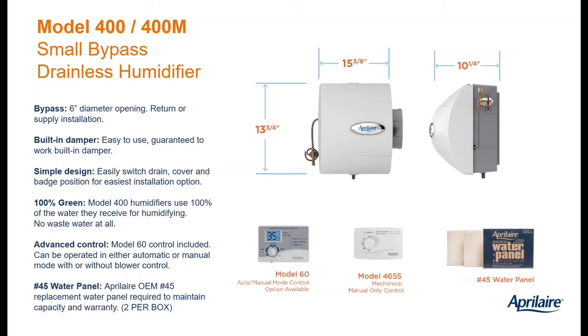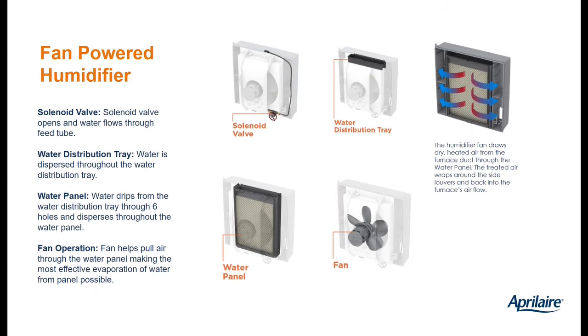And then there's the dimension showing the automatic humidistat, manual humidistat, and number 45 water panel. Here's our 700, the fan-powered humidifier. It uses a fan to help the air being moved by the HVAC blower to go through the water panel. So we don't have a bypass duct, we don't have the pressure differential created by the HVAC blower. We're using the fan to help pull that air through the water panel.